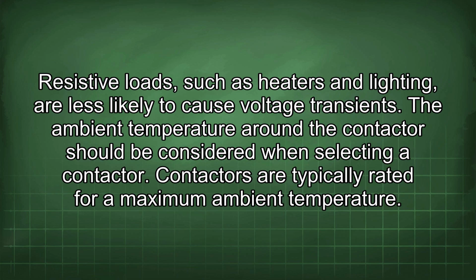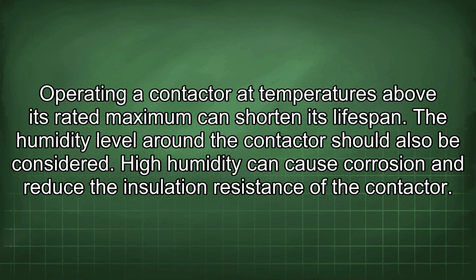The ambient temperature around the contactor should be considered when selecting a contactor. Contactors are typically rated for a maximum ambient temperature. Operating a contactor at temperatures above its rated maximum can shorten its lifespan. The humidity level around the contactor should also be considered. High humidity can cause corrosion and reduce the insulation resistance of the contactor.